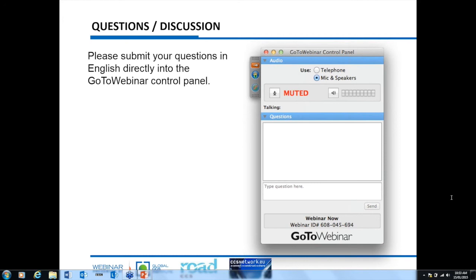Did you say the flue gas enters the stack at 50 degrees? And what's the final flue gas temperature? Right, the flue gas from the FGD enters the stack at about 50 degrees, so that's the current plant design. The capture plant would cool it down to about 35, and that would then mix. So you would have 50 degrees C flue gas from the FGD, 75% of the flue gas would be that, and then 25% would be at 35 degrees C coming from the capture plant, and they would mix. Off the top of my head, I don't know exactly what temperature that would give.